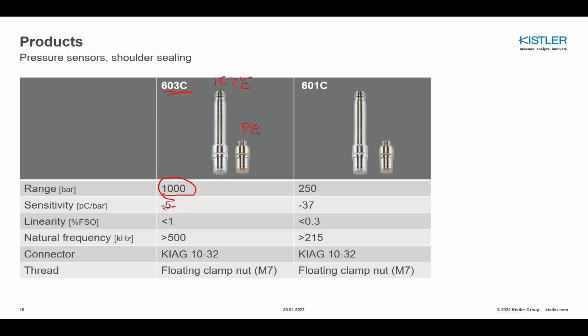Same sensor, same design, but different internal design is the 601C sensor. It's rated up to 250 bars with very, very high sensitivity, which is 37 picocoulomb per bar. So you can measure very precisely in the range of small pressures. You can see the linearity of the sensor is excellent. And again, it can be directly only with piezoelectric, that means a charge output, or IEPE output, or let's say ICP.